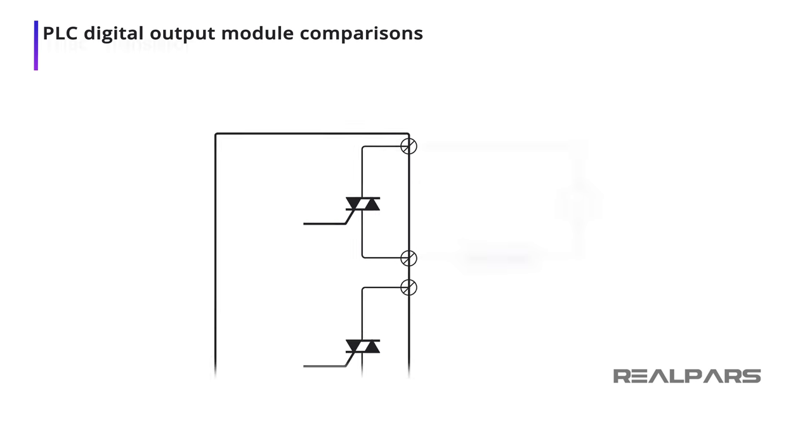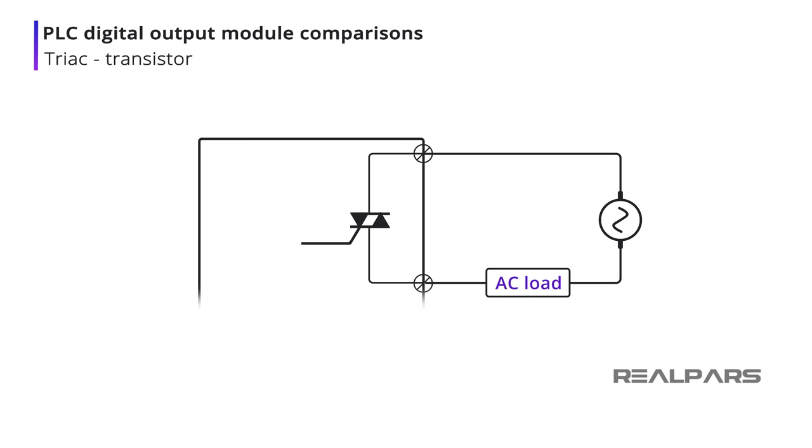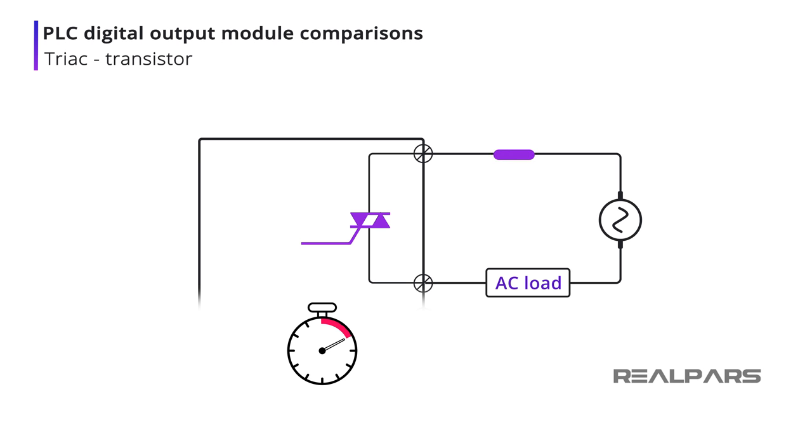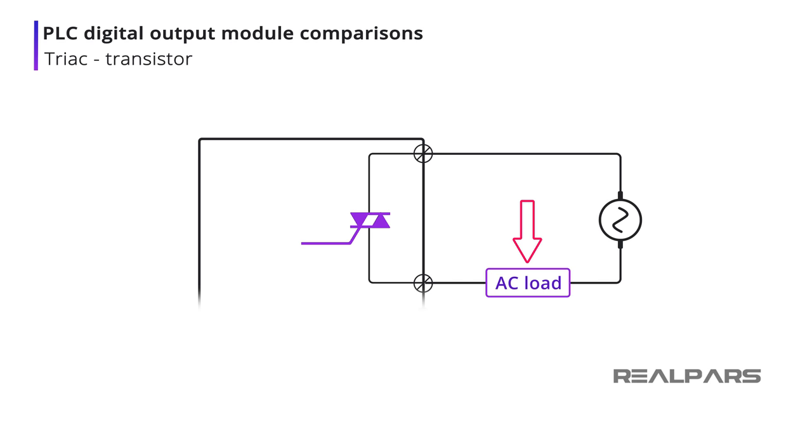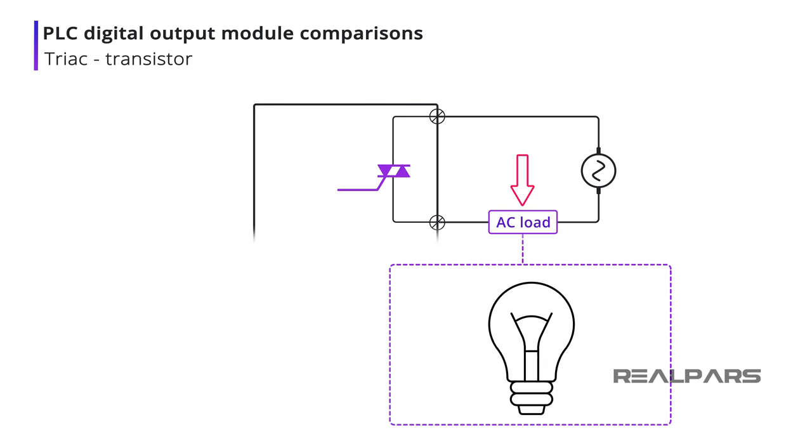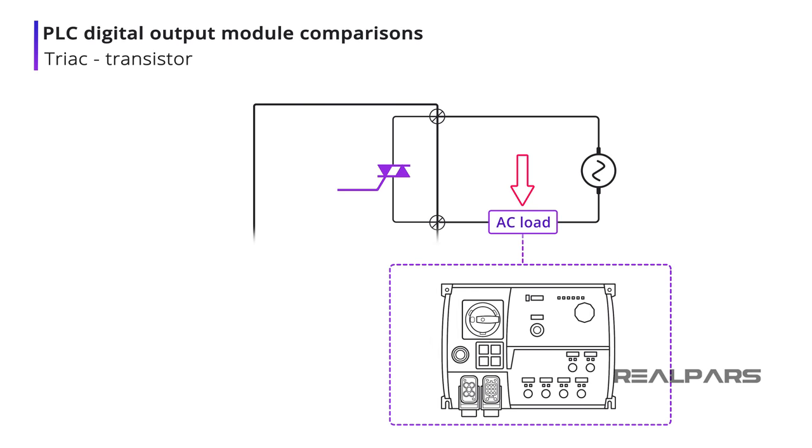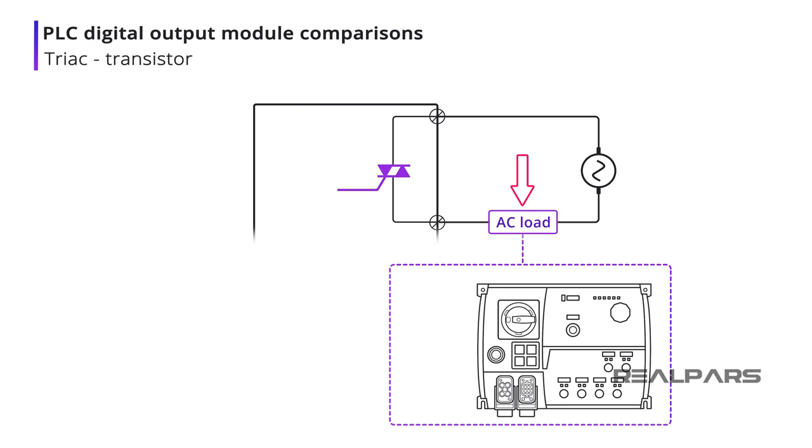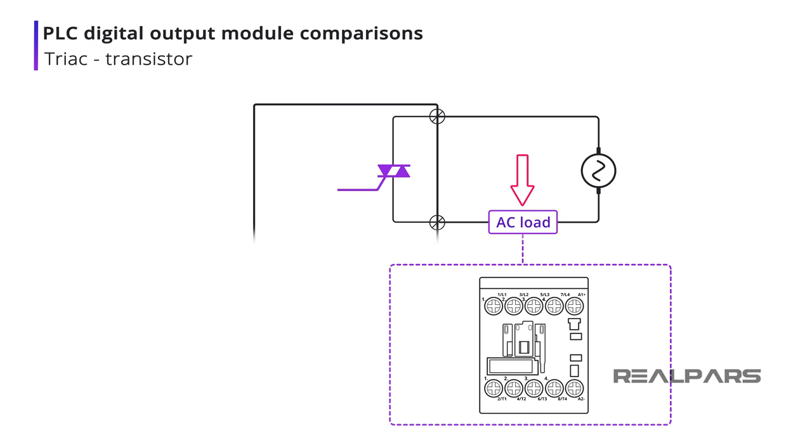A TRIAC output is used to control AC loads only. As with the transistor, a TRIAC is much faster than a relay. TRIAC outputs are suited to low power AC loads, such as lighting, motor starters, and contactors, with current ratings around 1 amp.